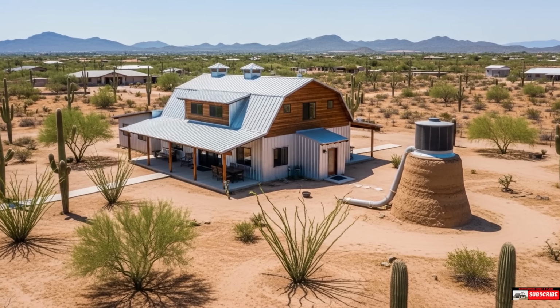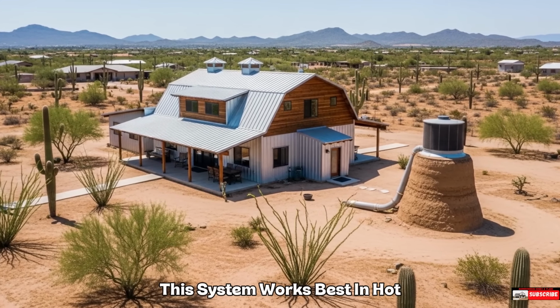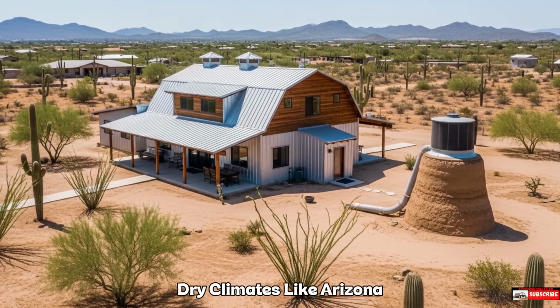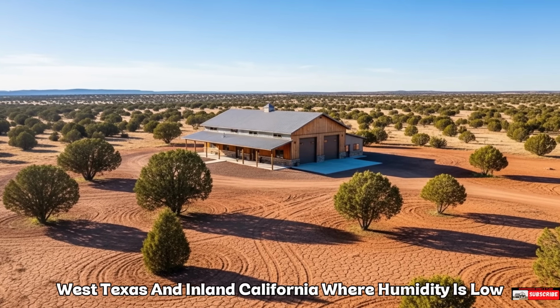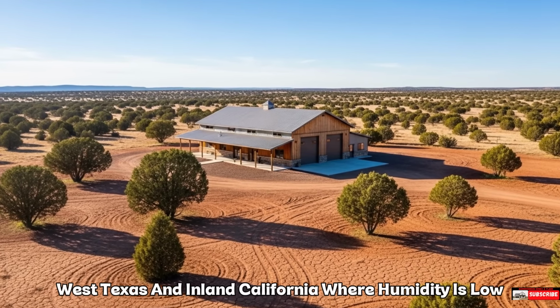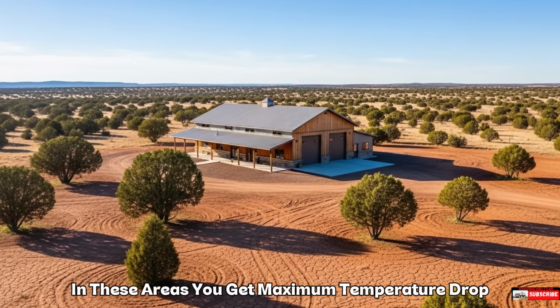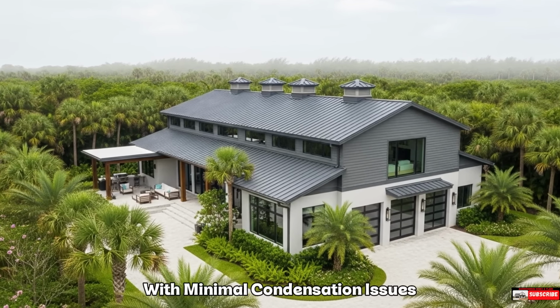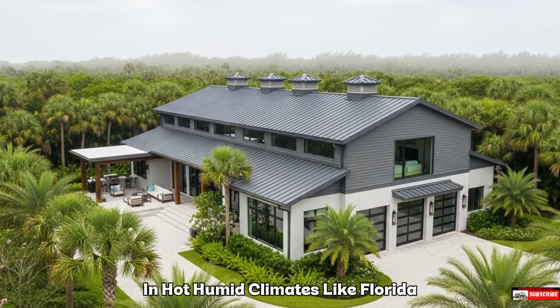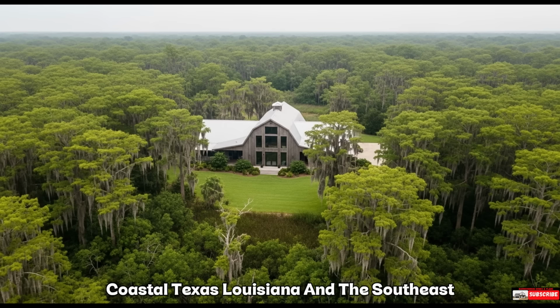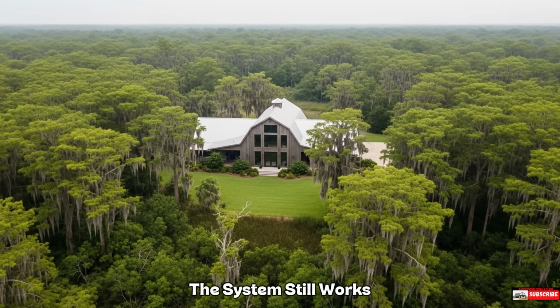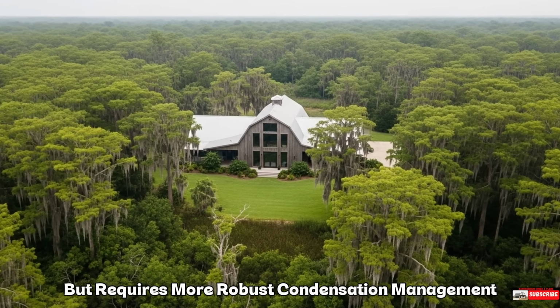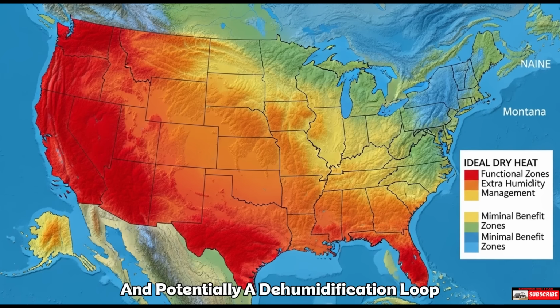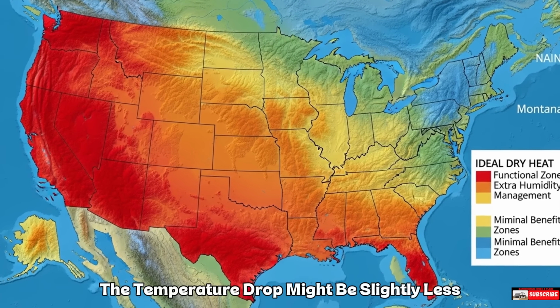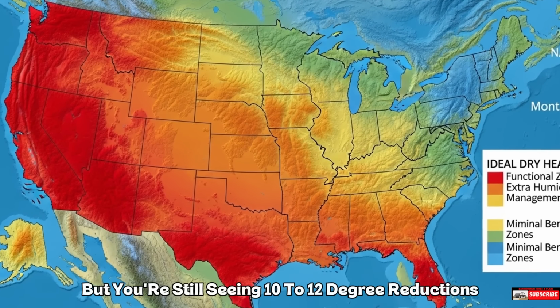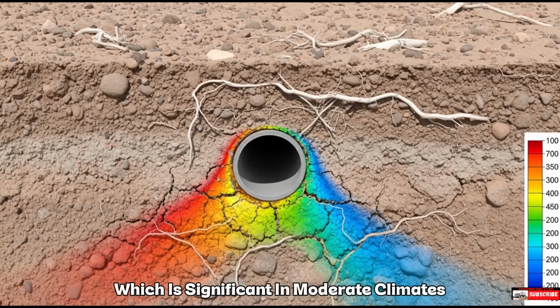Climate considerations. This system works best in hot, dry climates like Arizona, New Mexico, West Texas, and inland California, where humidity is low. In these areas, you get maximum temperature drop with minimal condensation issues. In hot, humid climates like Florida, coastal Texas, Louisiana, and the Southeast, the system still works but requires more robust condensation management and potentially a dehumidification loop. The temperature drop might be slightly less, but you're still seeing 10 to 12 degree reductions, which is significant.